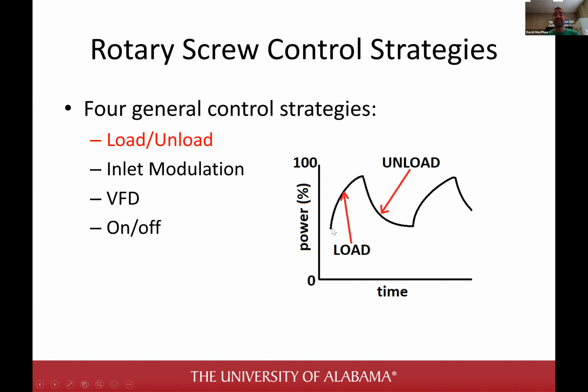It's a lot like a thermostat for an HVAC system. You set a pressure band, say between 105 and 115 psi. When the pressure in the system drops below 105, the compressor kicks on and loads until it hits 115, then it unloads. That's exactly what this graph is showing. I drew this using Microsoft Paint, so I apologize if it looks horrible, but I think it was better than me drawing with my hands.